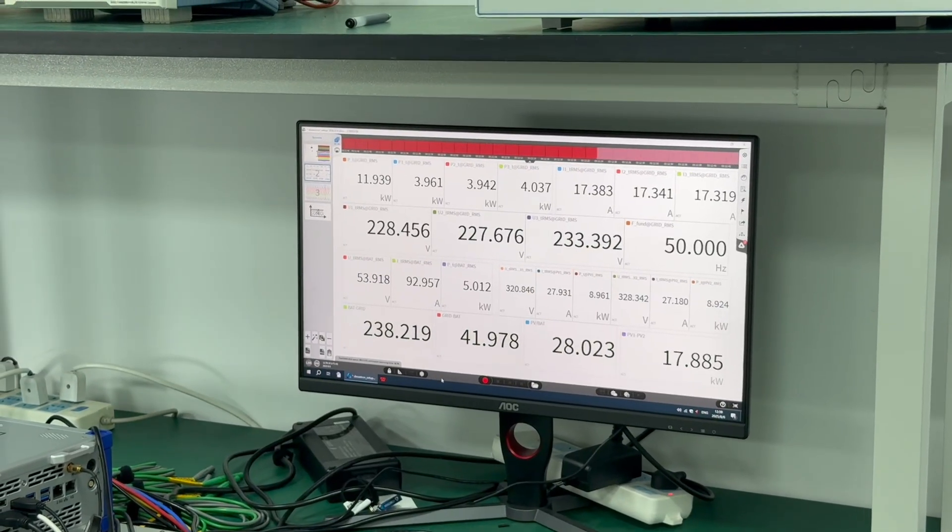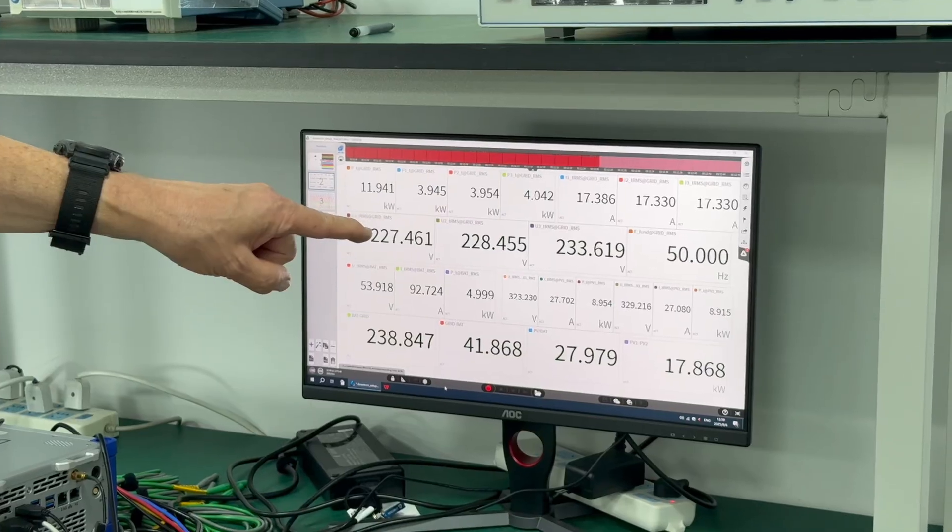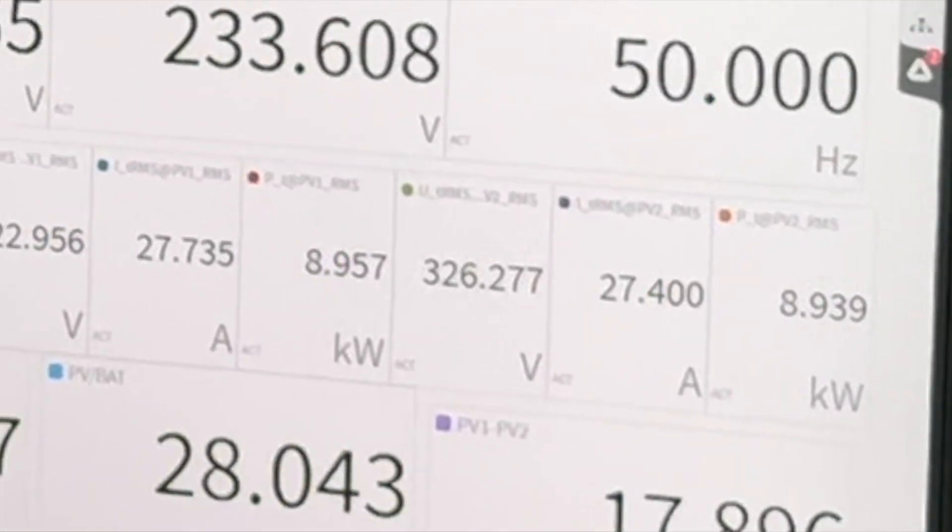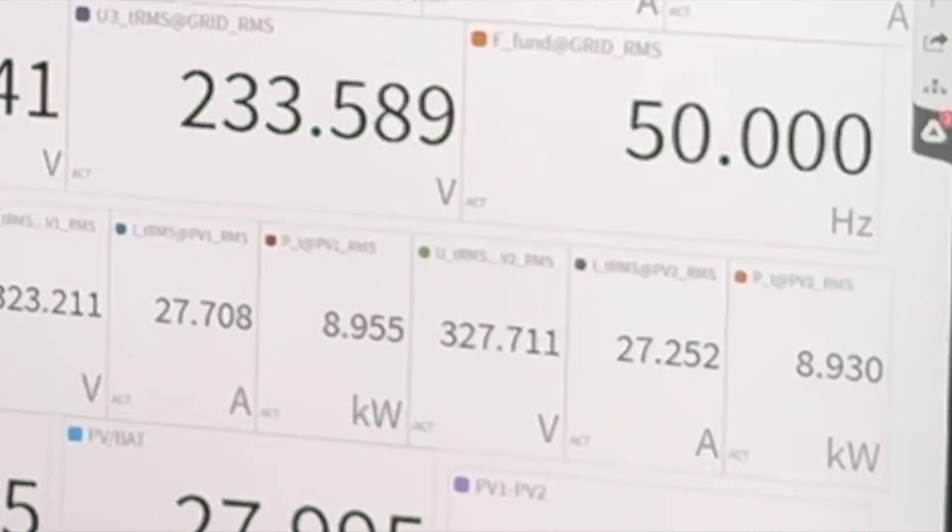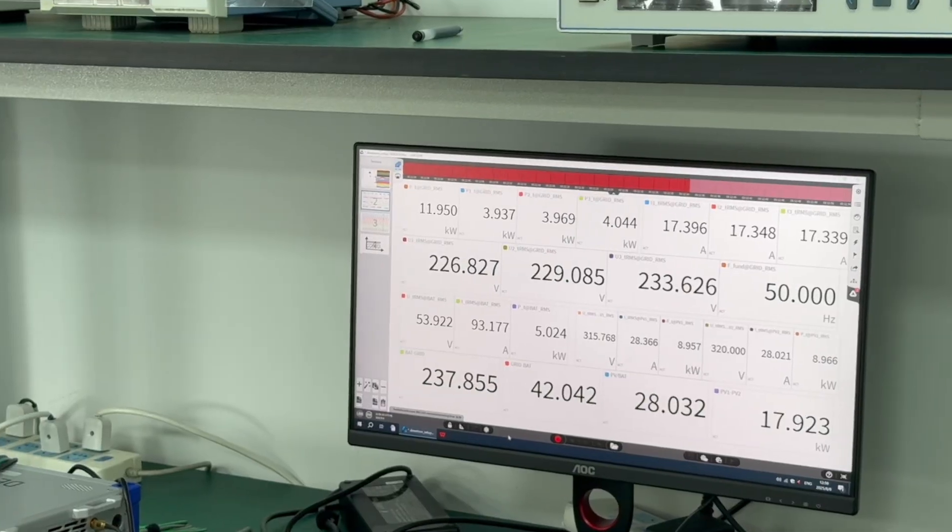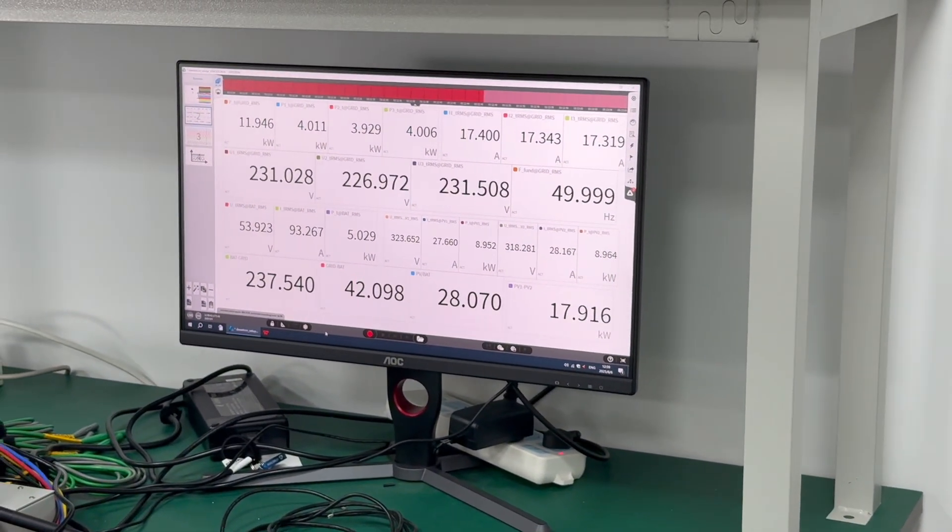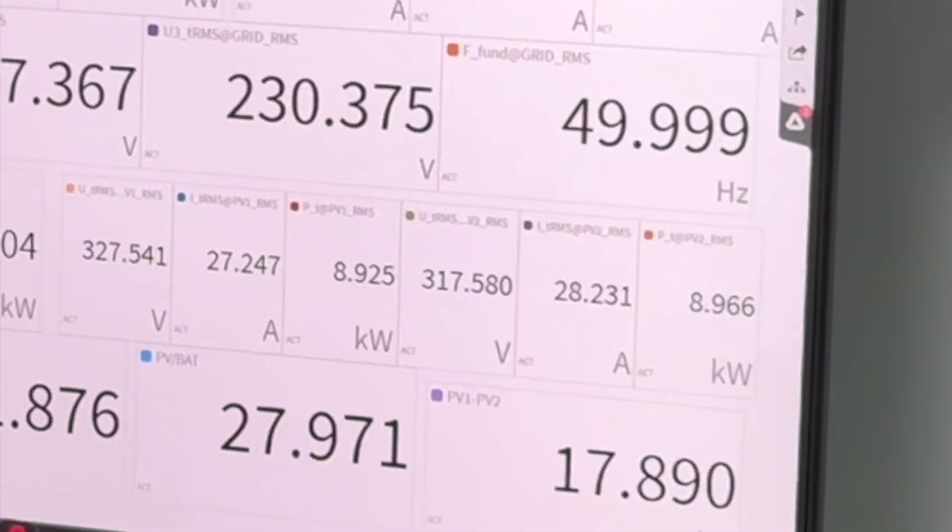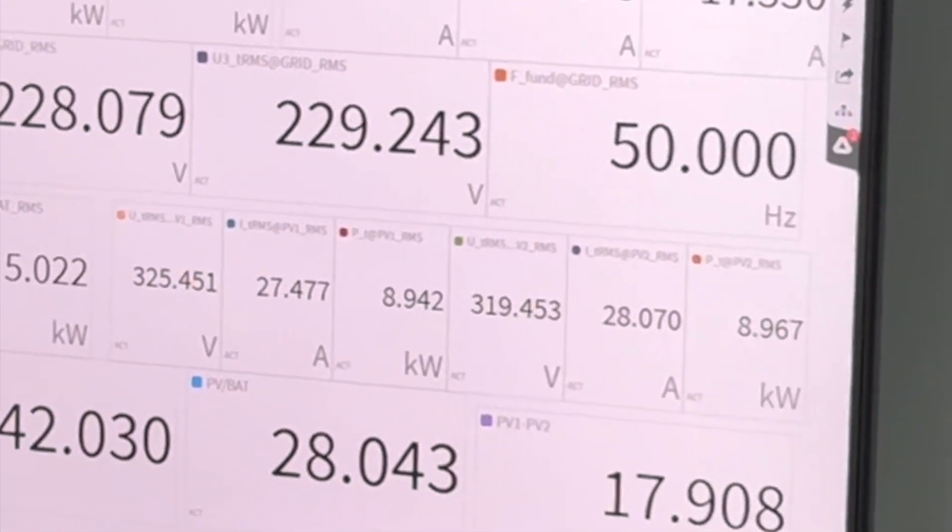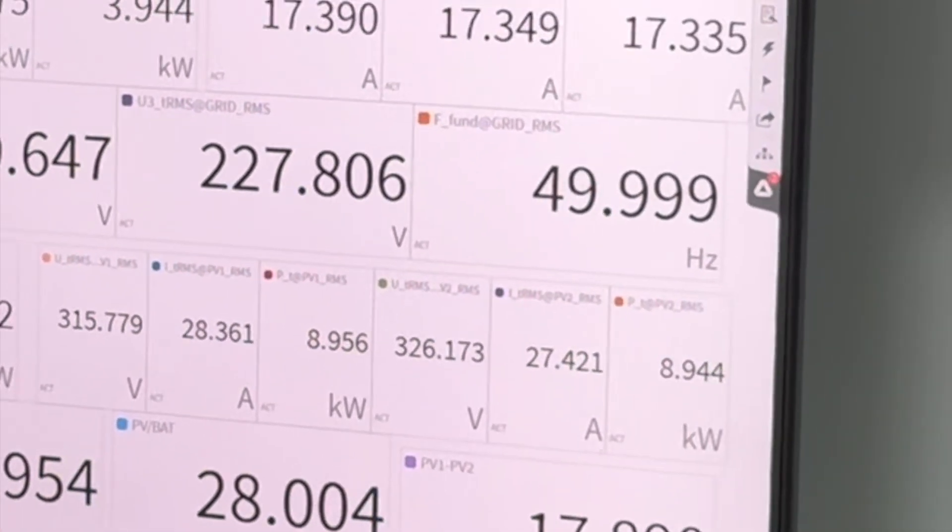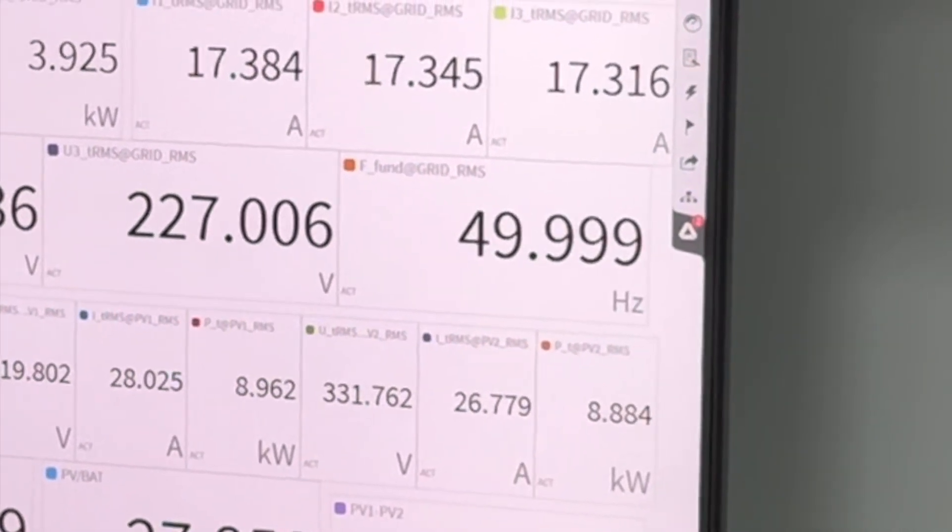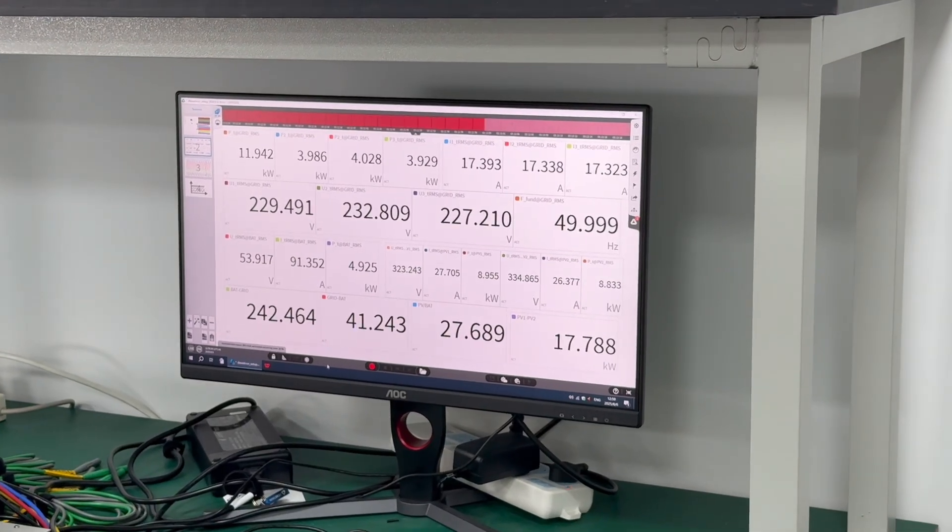Interestingly, if you look at the small numbers here, look at the bottom right-hand figure and here the other slightly across, you'll see a figure 8.93, 8.99. They are the MPPTs. Both MPPTs, there's two MPPTs in this unit. Both are running at 9,000 watts each. And in fact, you look at the current, it's almost 28 amp, 27.42, slight fluctuation, but they're running at 28 amps. This thing is handling two channels, 28 amps each at almost 18 kilowatts of MPPTs, processing it, running stone cold, absolutely cold.